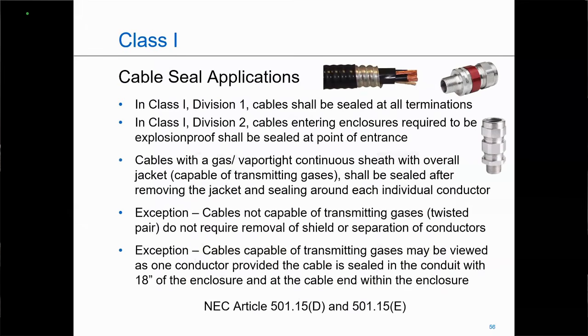We already started to allude to this to a certain extent, but when I have open cabling going into a Class 1, Division 1 enclosure, that cable is required to be sealed. So my gland is actually going to be a sealing gland. I'm required to seal all terminations in Class 1, Division 1. In Class 1, Division 2, if I'm going into an enclosure that's required to be explosion-proof, such as the motor starter or the circuit breaker, again, that's required to be sealed, and I need to use the sealing fitting. But if I'm entering an enclosure that's not required to be explosion-proof, such as my terminal box, I'm just going to use the gland that has been approved for that particular cable or application, and that gland does not have to be a sealing fitting gland.